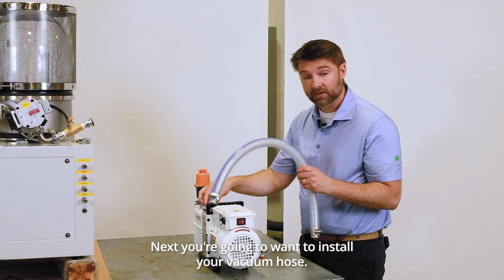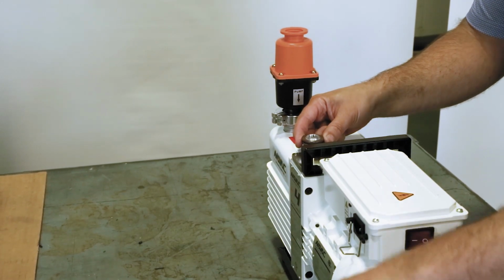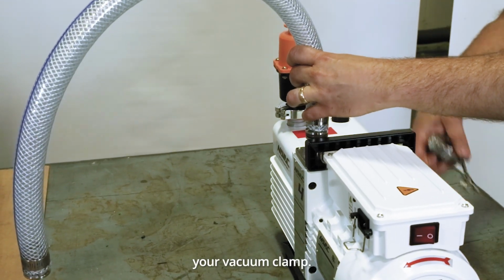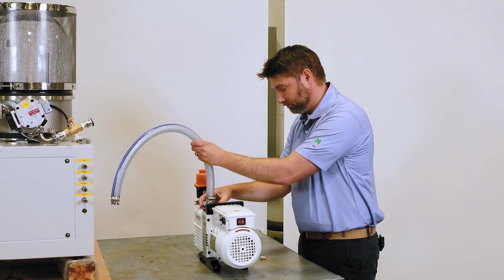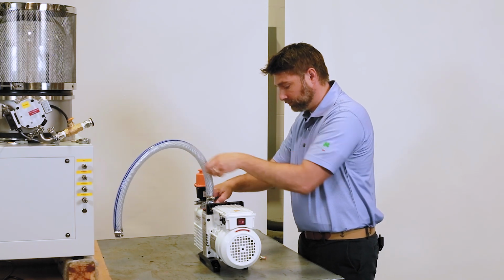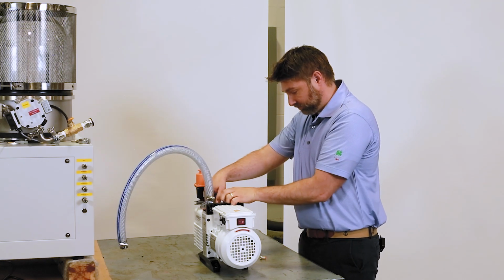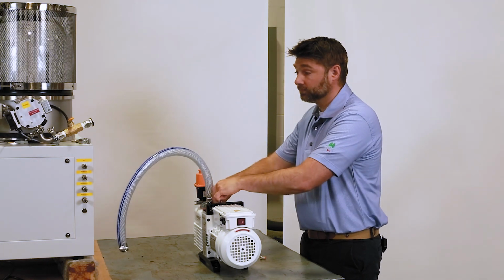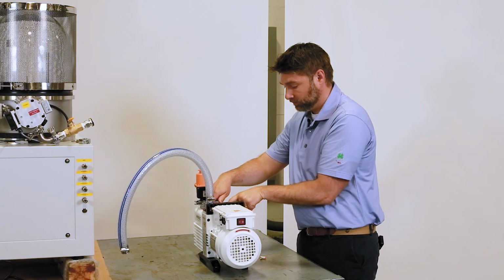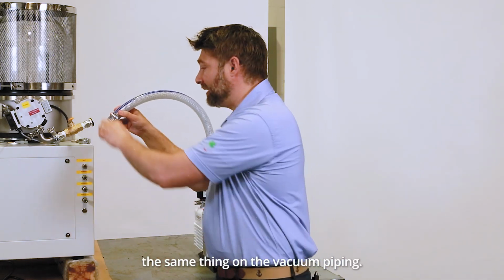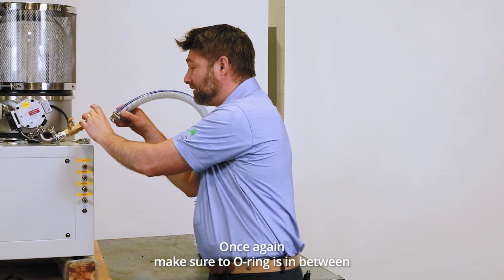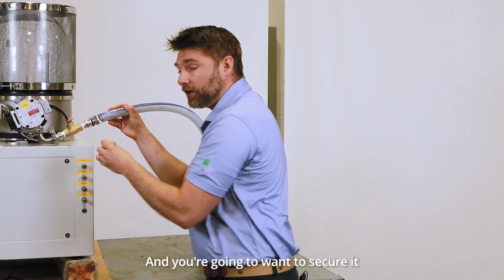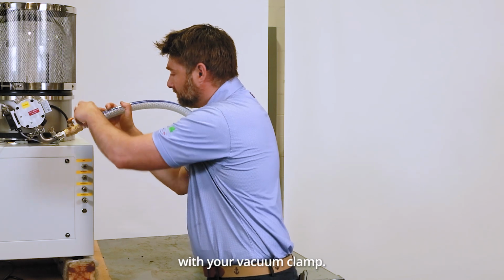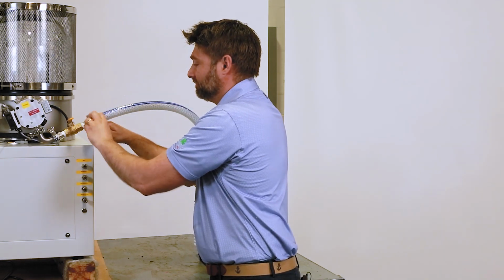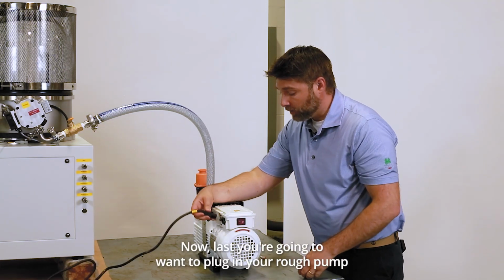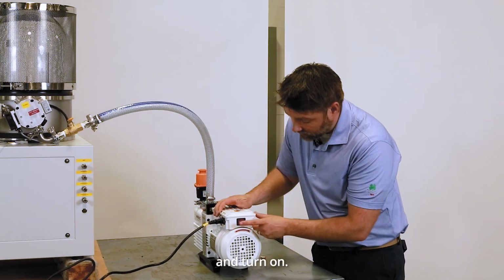Next, you're going to want to install your vacuum hose. Same thing. Place your O-ring in between the flange and the vacuum hose, and install your vacuum clamp. And you'll want to do the same thing on the vacuum piping. Once again, make sure the O-ring is in between the flange and the vacuum hose, and secure it with your vacuum clamp. Now last, you're going to want to plug in your rough pump and turn it on.